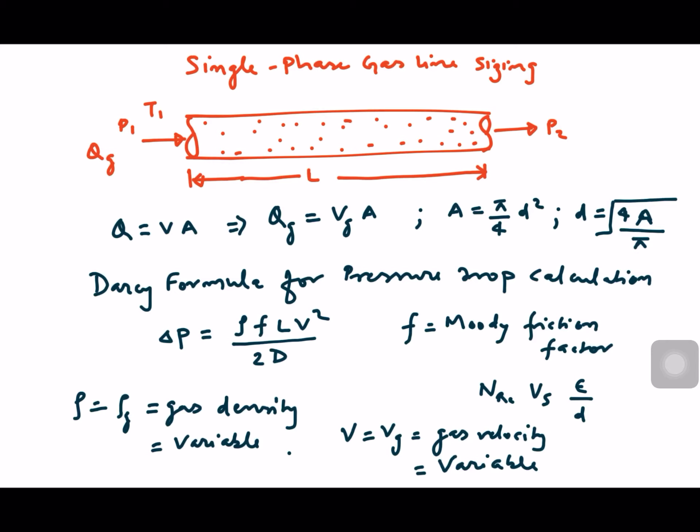Let's say we have a pipeline of length L, inlet pressure P1, outlet pressure P2, inlet temperature T1, and inlet gas flow rate Qg. In previous videos I have explained line sizing for liquid lines. There we use a simple formula: Q = AV. From that formula we can calculate the velocity of the fluid for the given volumetric flow rate Q in cubic meters per second, using the assumed diameter to calculate the cross-sectional area of the pipeline.